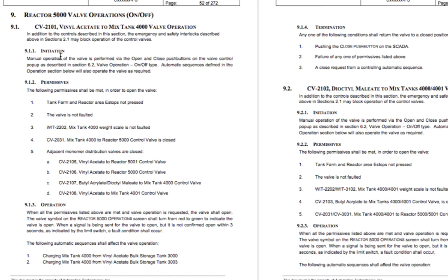Same thing with the valves — we've got some on/off valves right here. It tells what initiation is, what makes them open or close depending upon how they fail — whether it's fail-closed, fail-open, or fail-last — and then permissives, operation, and termination. It's all pretty much the same whether you're dealing with valves, motors, or different pieces of equipment. You might have to be a little more flexible if something is outside the realm of how things normally operate.